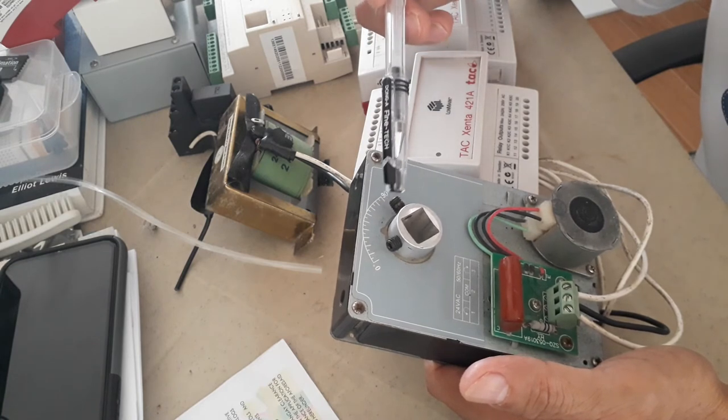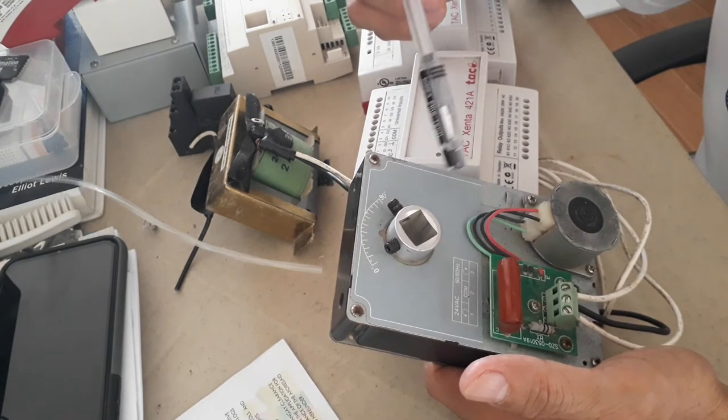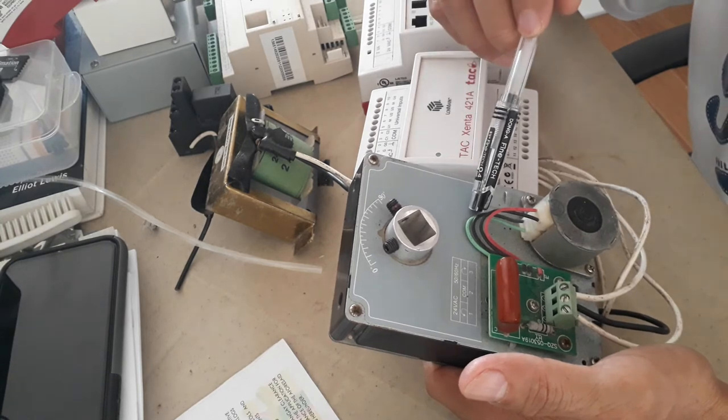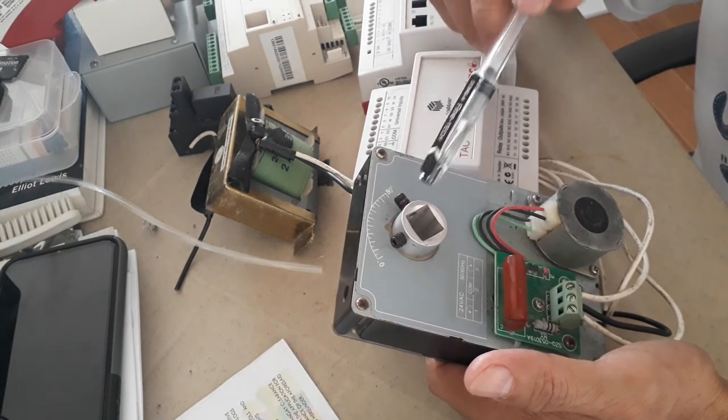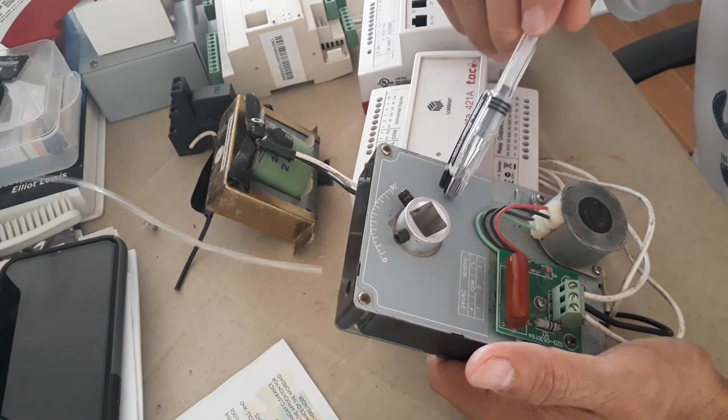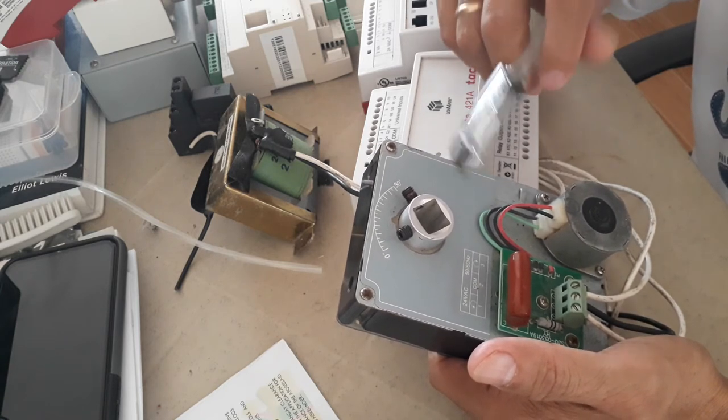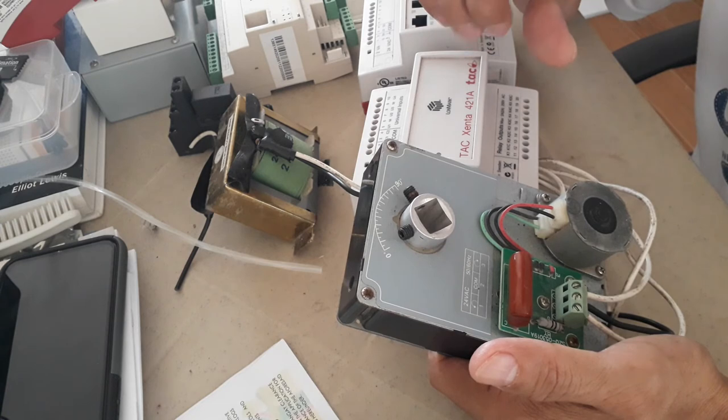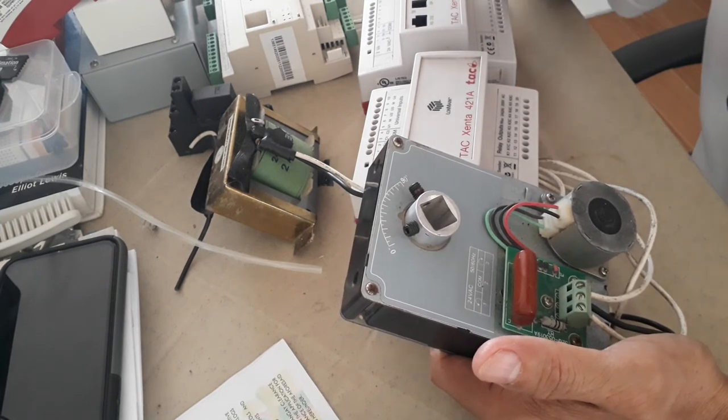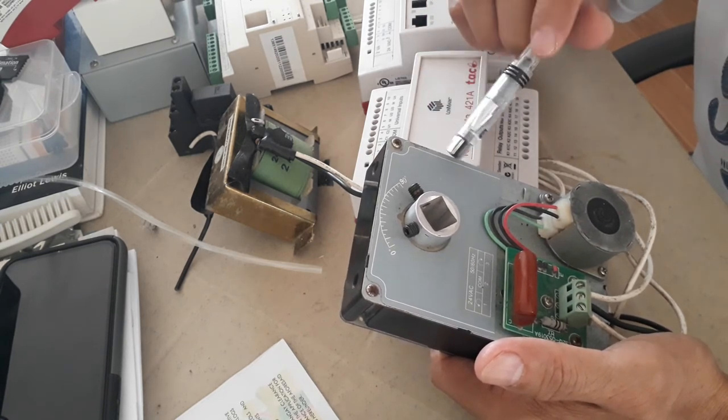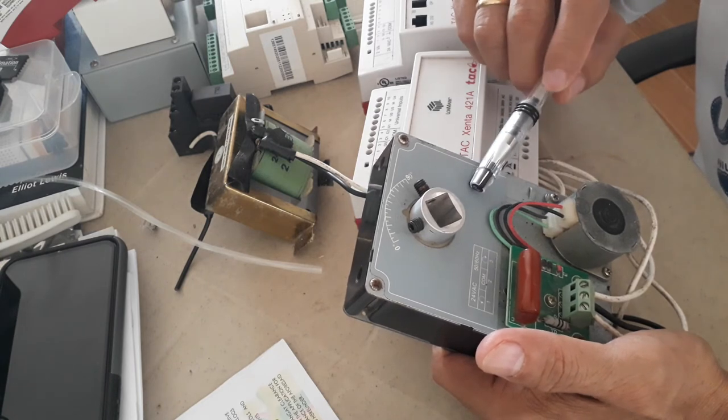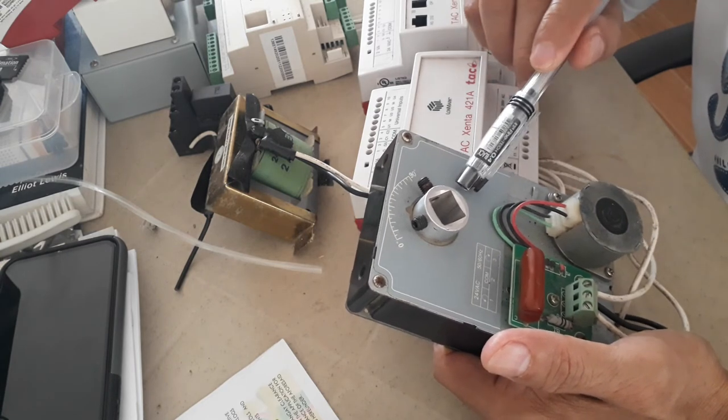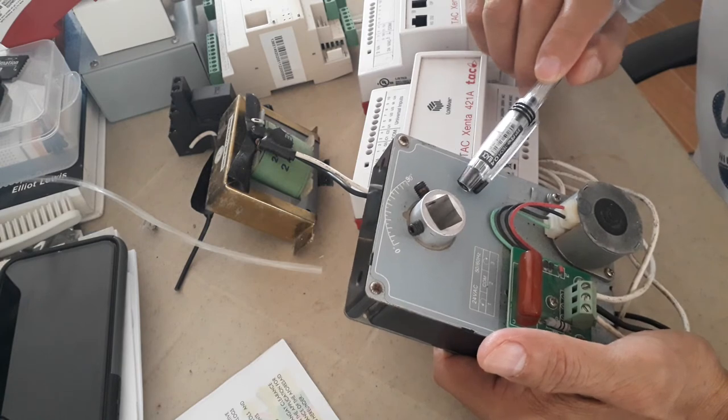Then I have given you already an idea how to prevent this damper actuator from burning or being damaged by making sure that the damper installed in the site can be freely opened and closed manually. And of course, always check the torque requirement of the damper installed in the site before ordering your damper actuator.